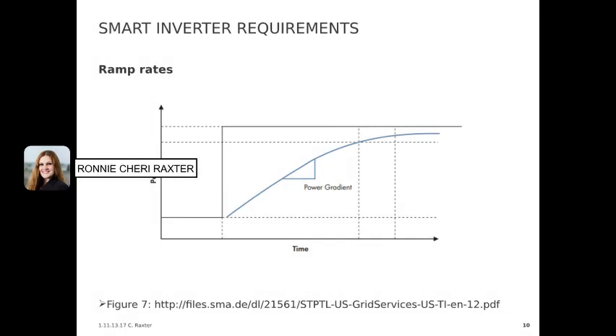The next setting is ramp rates. Again, this has to be activated. This function defines how the DERs will turn on, because some DERs, PV most notably, can ramp up, which is a turn on, faster than traditional electrical generation. The Rule 21 requirement has reduced the ramp rate from 100% to 60% to allow more time to ramp back on traditional generation as PV DERs are ramping up in the morning.